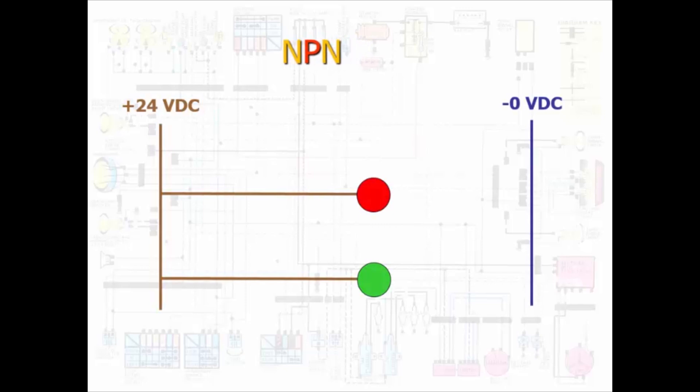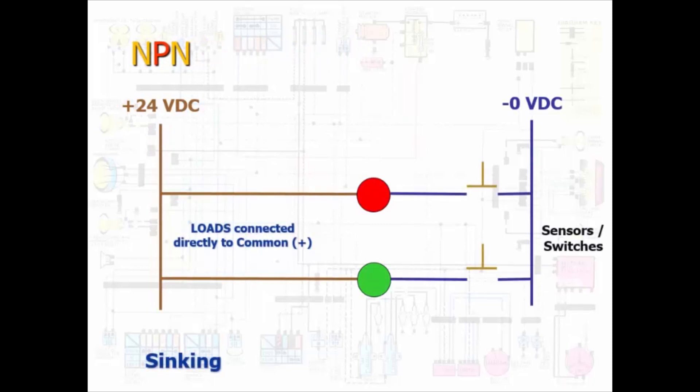This is an NPN circuit where the loads are already powered from the positive common but still need some switch input to connect the circuit to the negative common. The voltage is trying to sink from 24 volts down to zero.